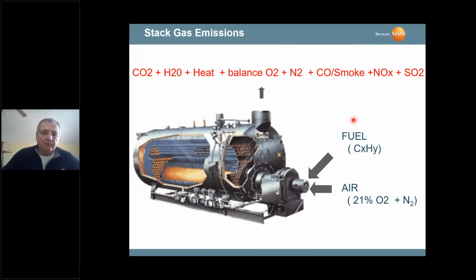And if you look at the top there, you'll see the byproducts of combustion. Hopefully a lot of these formulas you already know. Carbon dioxide, which is CO2, is a byproduct of combustion. H2O is water, so we do have water. That's why combustion analyzers have water traps. We have stack temperatures, or heat going out the stack. We want to try to minimize that heat because we really want the heat maintained in the boiler tubes or in the heat exchanger of the furnaces.